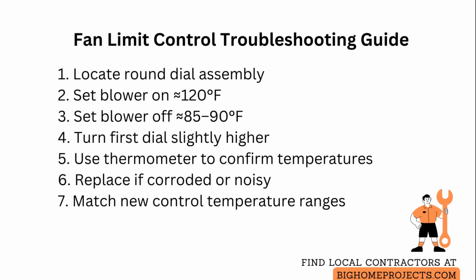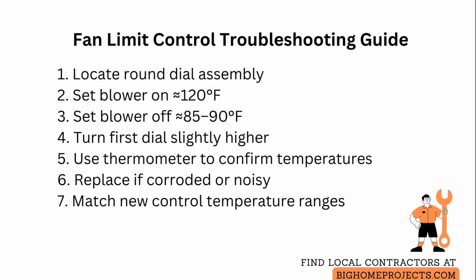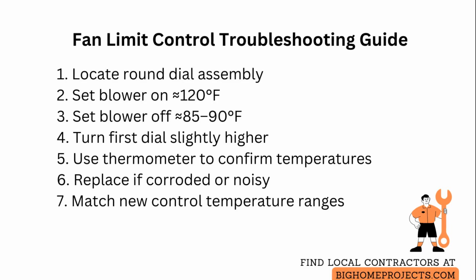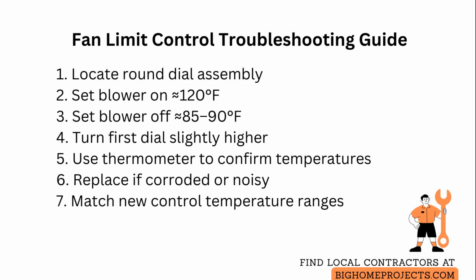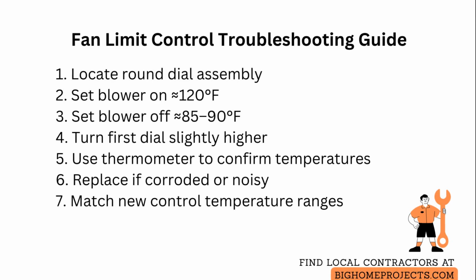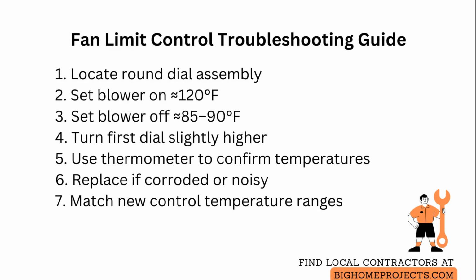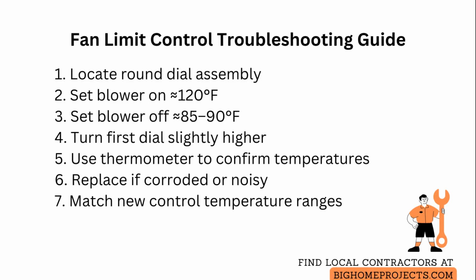Verify the blower on temperature is set around 120 degrees Fahrenheit, and the blower off temperature is set around 85 to 90 degrees Fahrenheit. These are typical targets for older systems, though the exact numbers can vary with your furnace model. If the blower on setting is too low, the blower may stay on continuously because the control never reaches the off threshold, so carefully turn the first dial a few degrees higher and recheck operation after a full heat cycle.